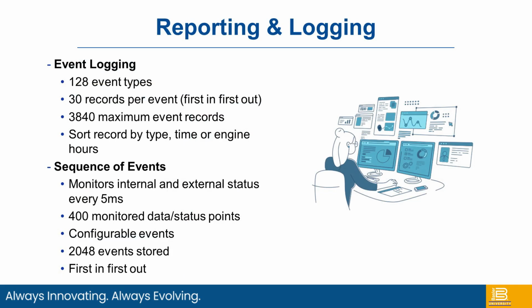Reporting and logging. For our event logging, we have 128 event types. There are 30 records per event. It is first in, first out. There's a maximum of 3,840 records that we can store. You can sort the records by type, time, or engine hours.